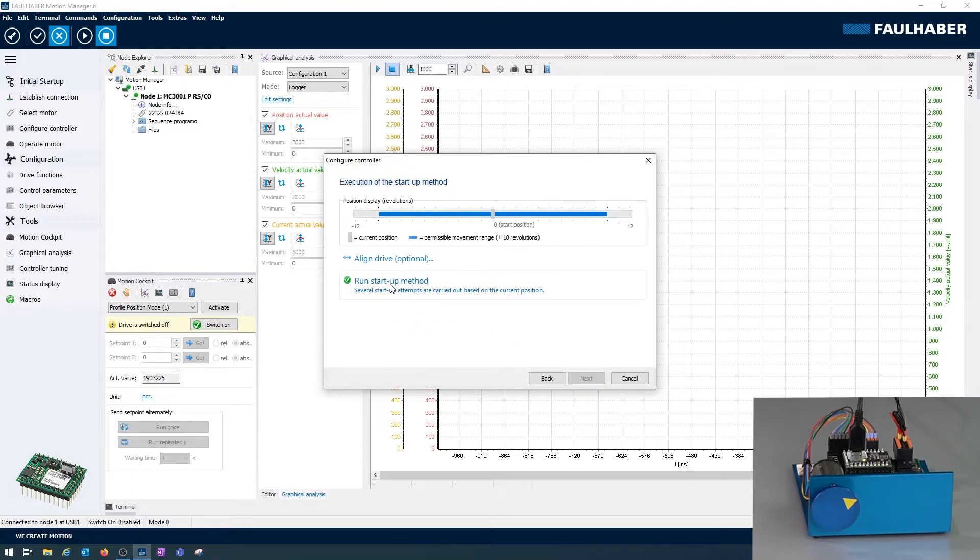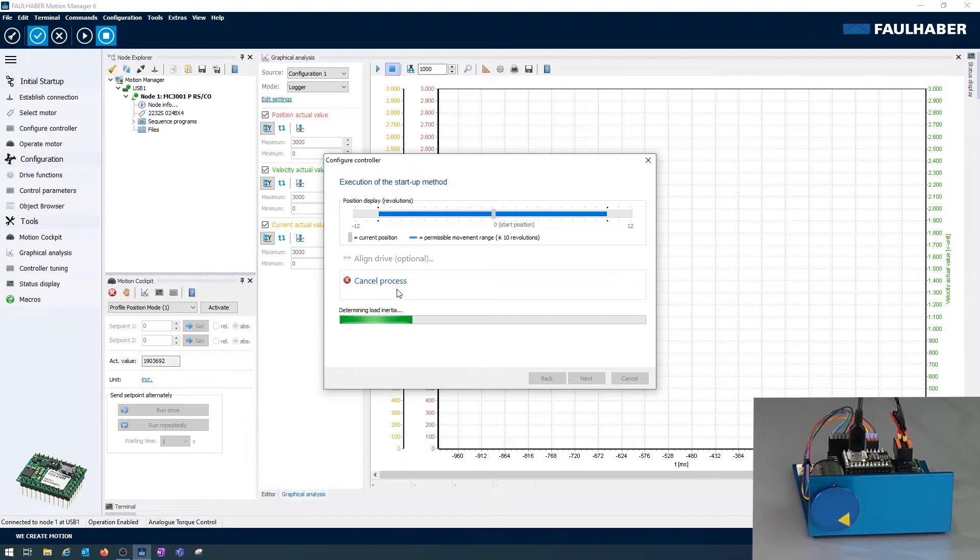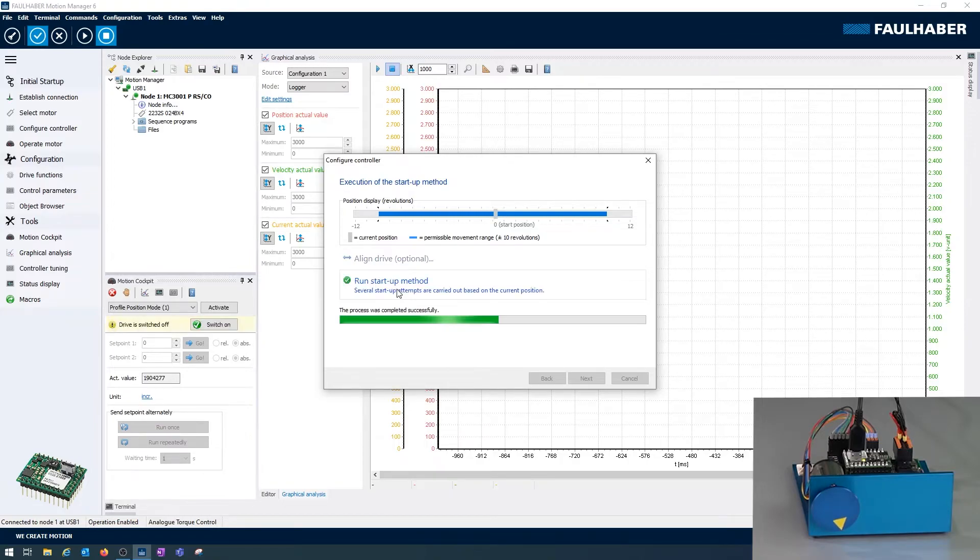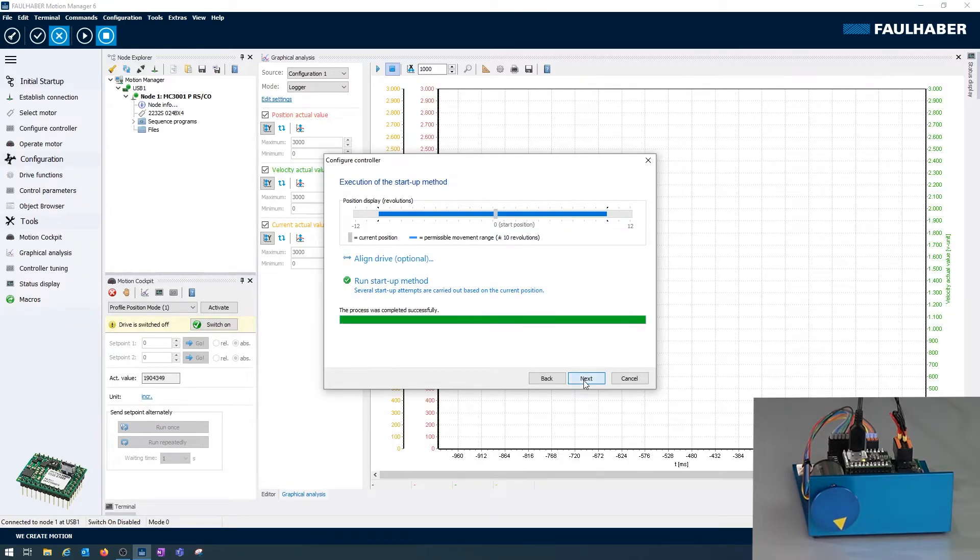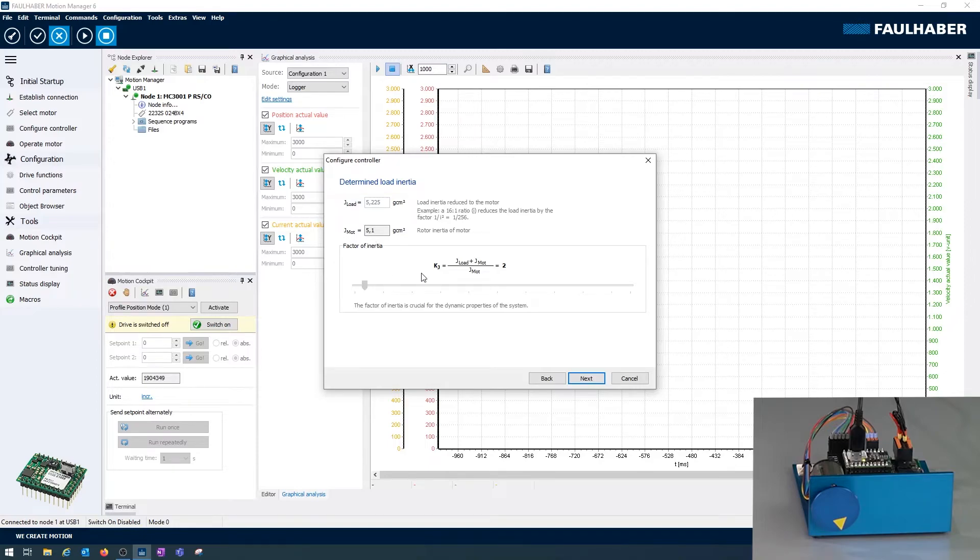Next I start the identification. Again the drive is moving, it's shaking a little bit. Out of the reaction of the drive the inertia of my small disk is identified to be roughly the same size as the inertia of the motor, which is an inertia factor of two. And two is more or less the ideal value for high dynamics operation.